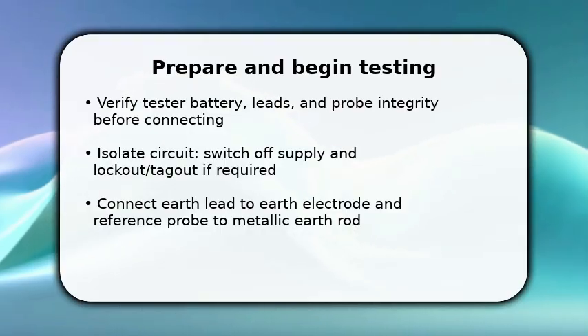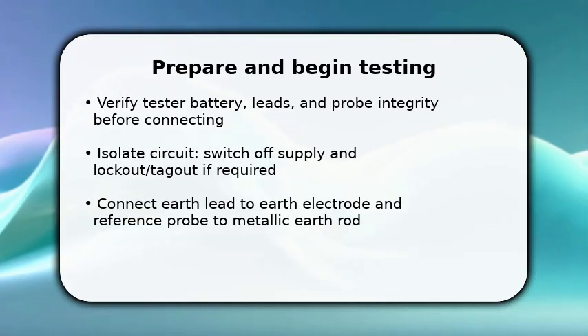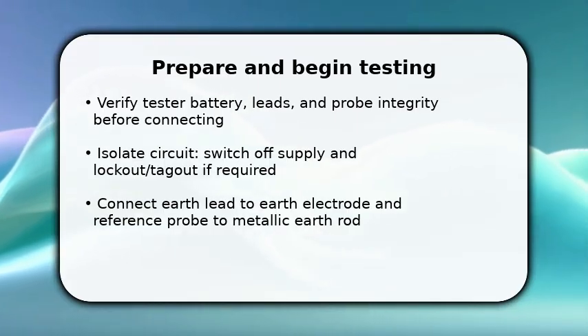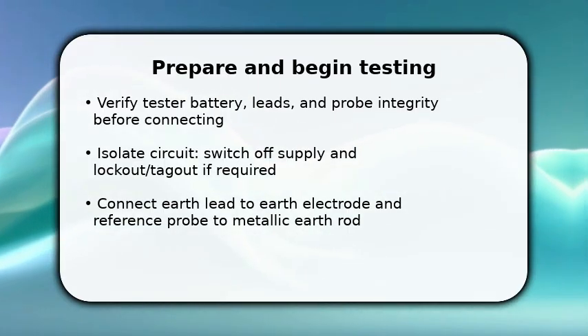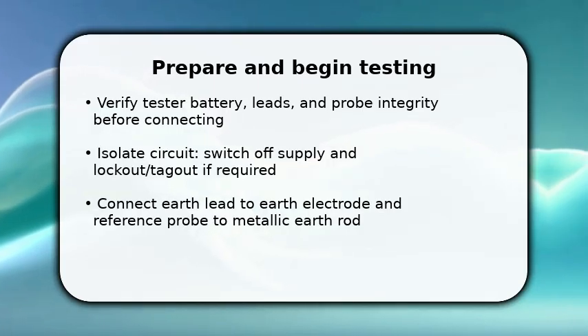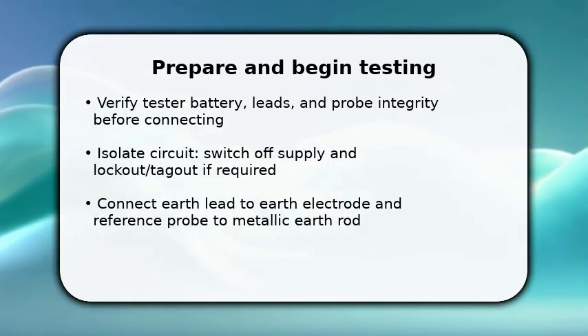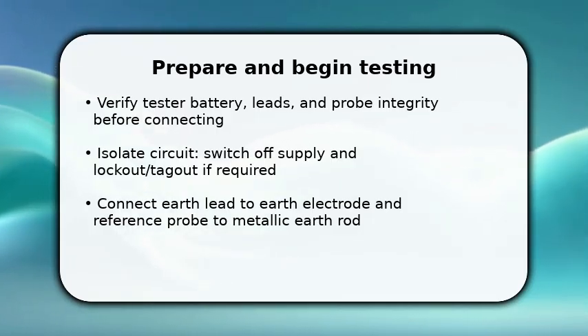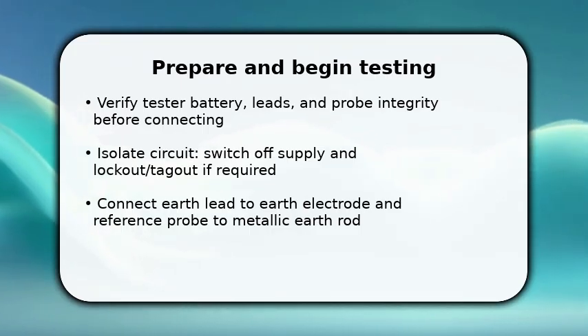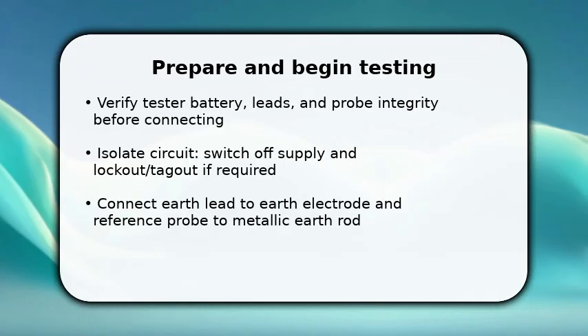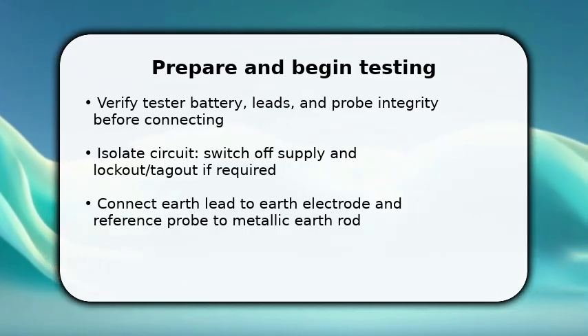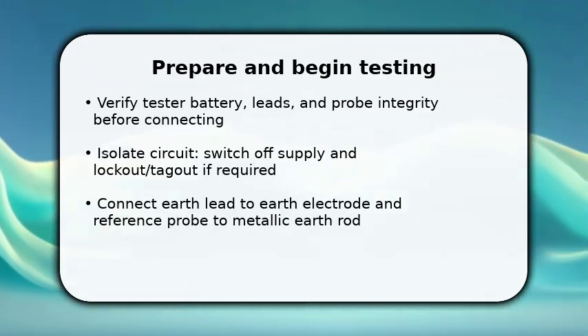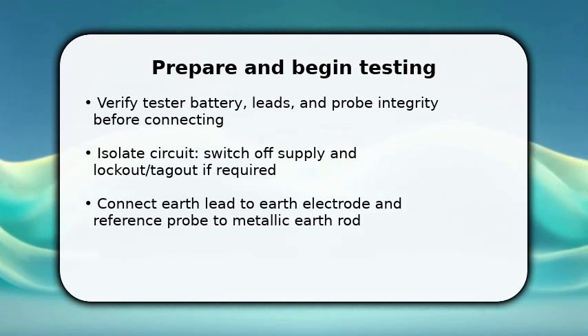You begin by confirming the tester is powered and leads are intact. This prevents false readings. Once done, isolate the circuit and apply lockout/tagout if needed so you can work safely. Connect the earth lead to the main earth electrode and place the reference probe at the specified distance from the rod. Make sure the soil is moist or dampen with water to reduce resistance. These first actions let you capture reliable baseline continuity measurements and avoid repeat tests.